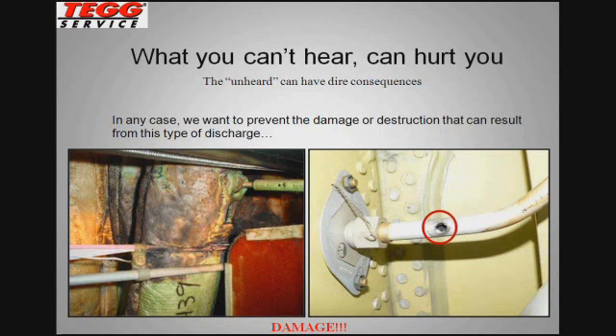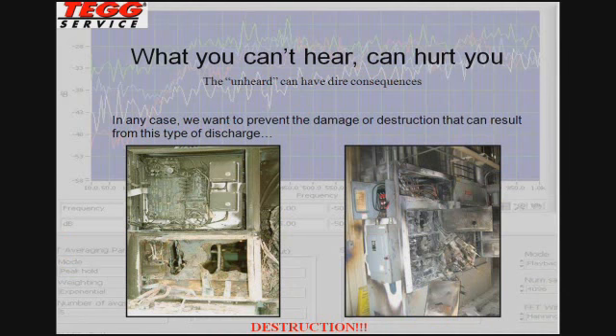And ultimately, we do not want to see any type of destruction that traditionally is not limited to the component of failure alone. If there's a catastrophic failure in a piece of equipment, the upstream and downstream components can be at risk of sustaining damage or destruction as well. And that's the name of the game, is we want to prevent this from happening. Arcing is certainly an anomaly that can lead to this type of destruction. So the earlier you find it, the more likely you are to prevent a failure.